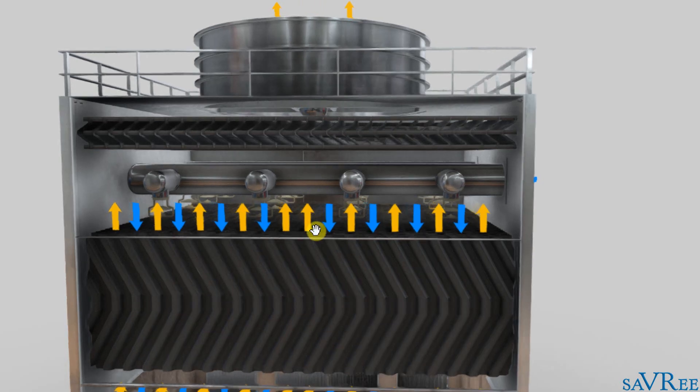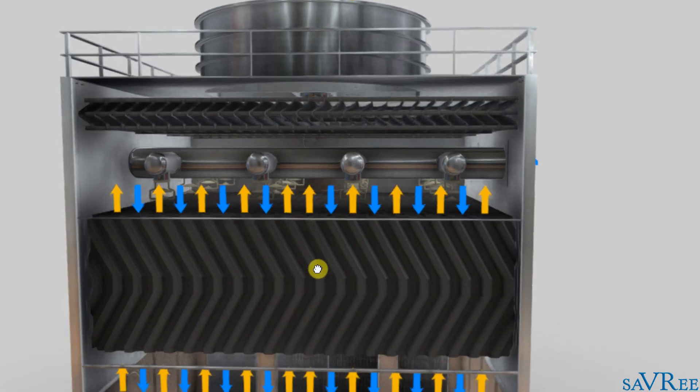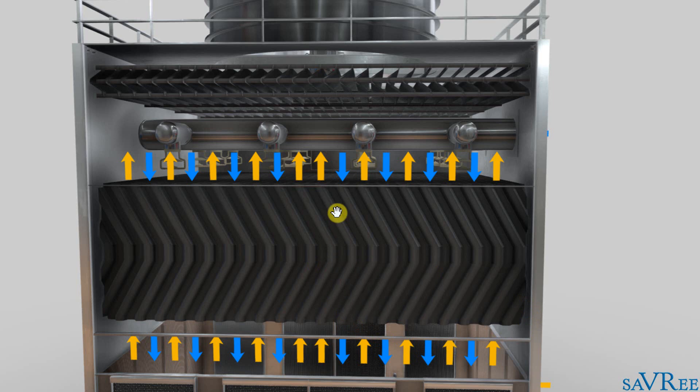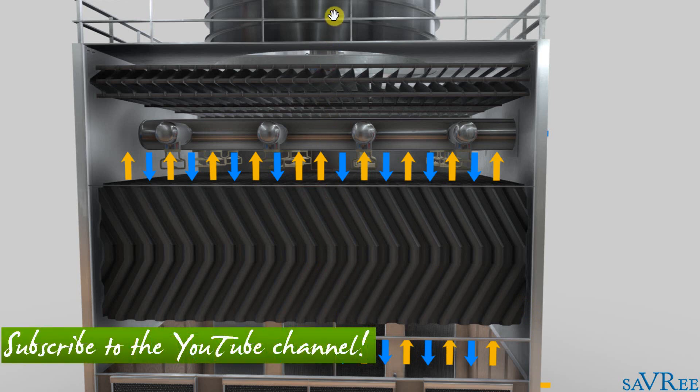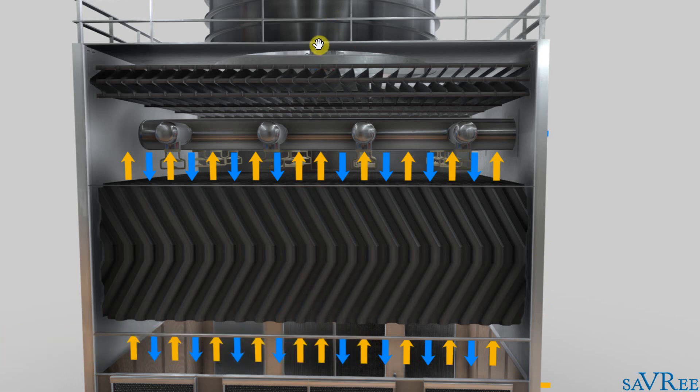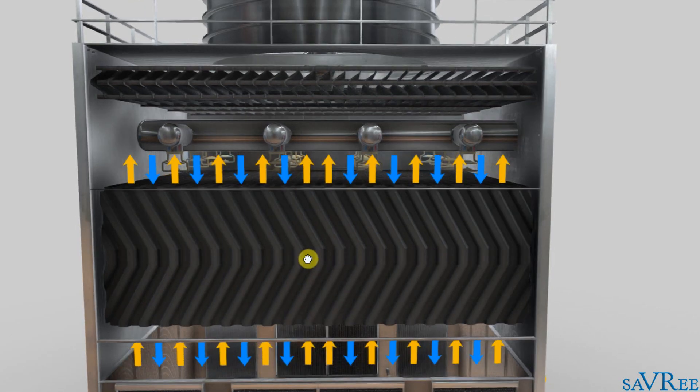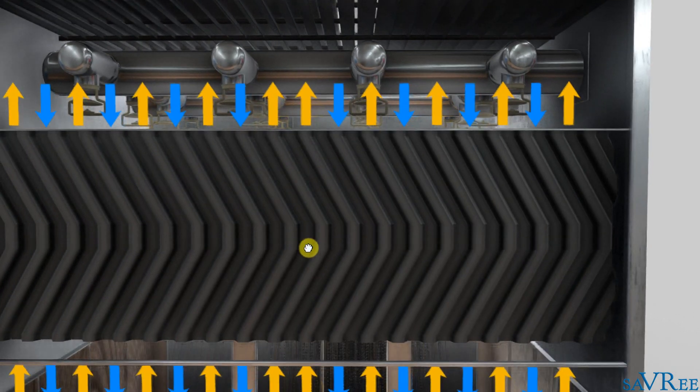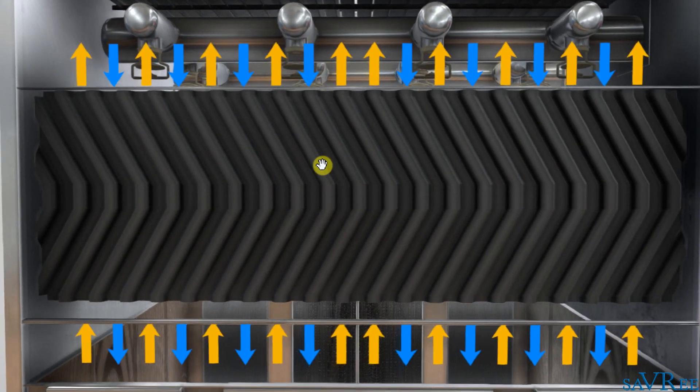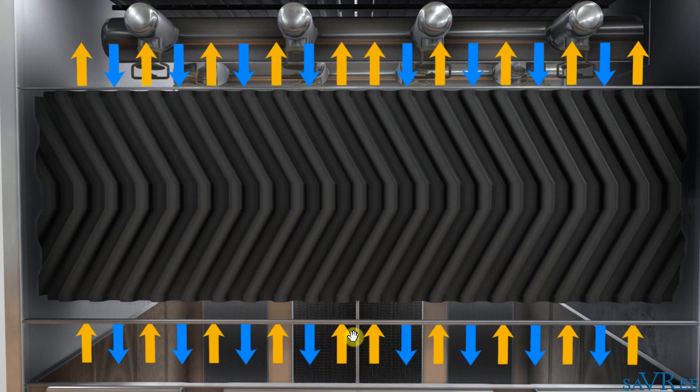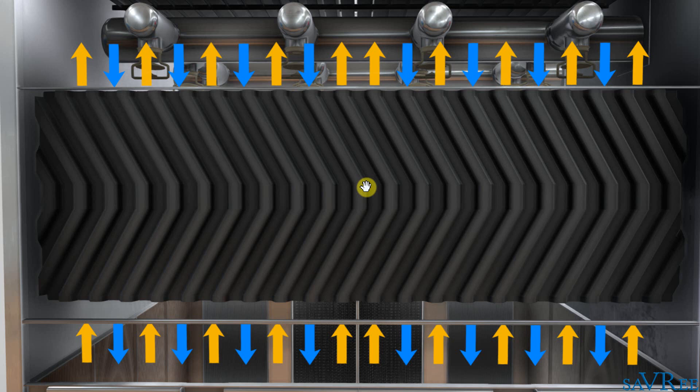This is an induced draft tower. It's induced draft because the air is passing through the fill or over the fill before it reaches the fan. So just remember that if it's passing through or over the heat exchanger prior to reaching the fan then it is an induced draft cooling tower. We can see on our arrows here that we've got blue arrows going down due to gravity and we've got yellow arrows going up, and the air is being drawn up by the fan. Notice that the arrows are pointing in opposite directions, they're 180 degrees apart. So they're flowing counter current to each other and that's why we call this type of tower a counter flow cooling tower.